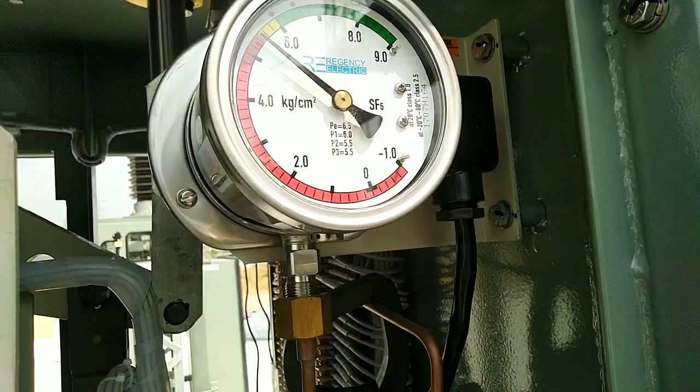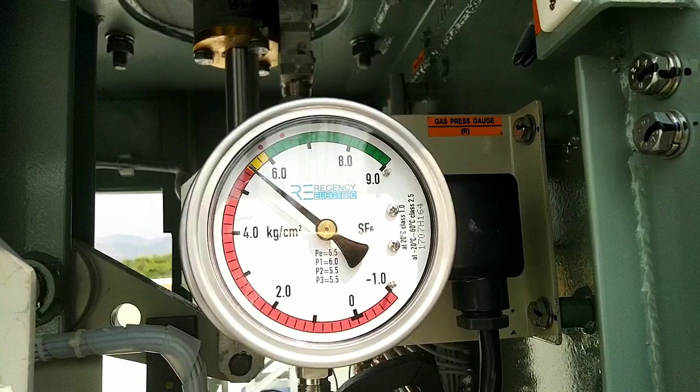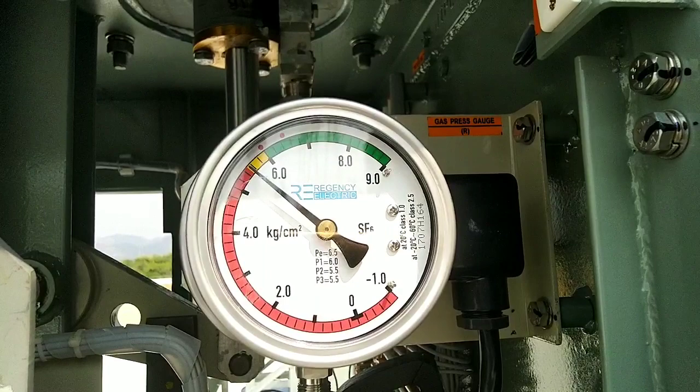After filling up to 5.5 pressure bar, the NO contact will make and the lockout will release. After 6.0 bar, the alarm contact will open. After 5.5 bar, the lockout contact will open.